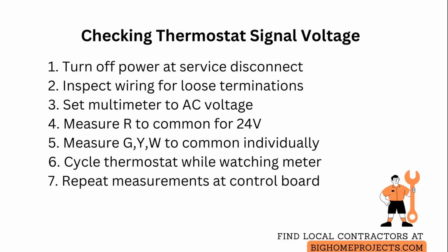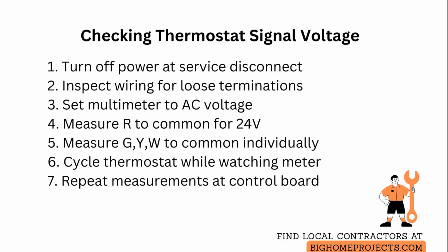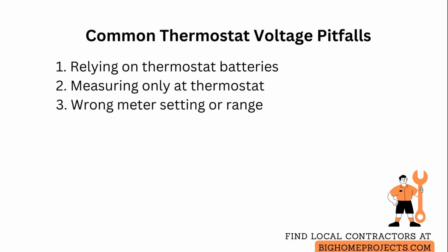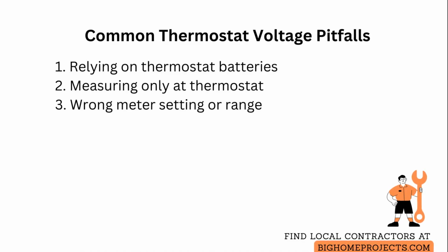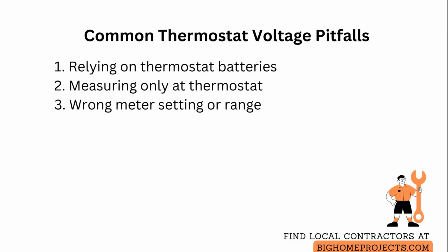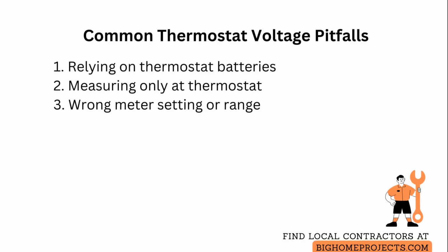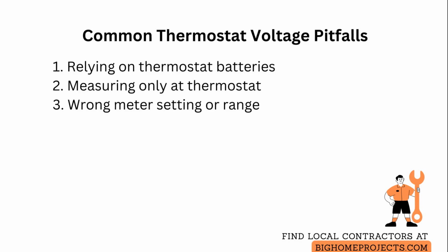Finally, use the meter to check for shorts to ground and inspect wire insulation and routing for pinches or staples that can cause intermittent voltage loss. Common mistakes include relying on battery-powered thermostats without checking the system transformer, which can show proper internal battery voltage but not supply 24 volts to the control circuit. So always test at the thermostat base with power on and verify the transformer output at the control board.